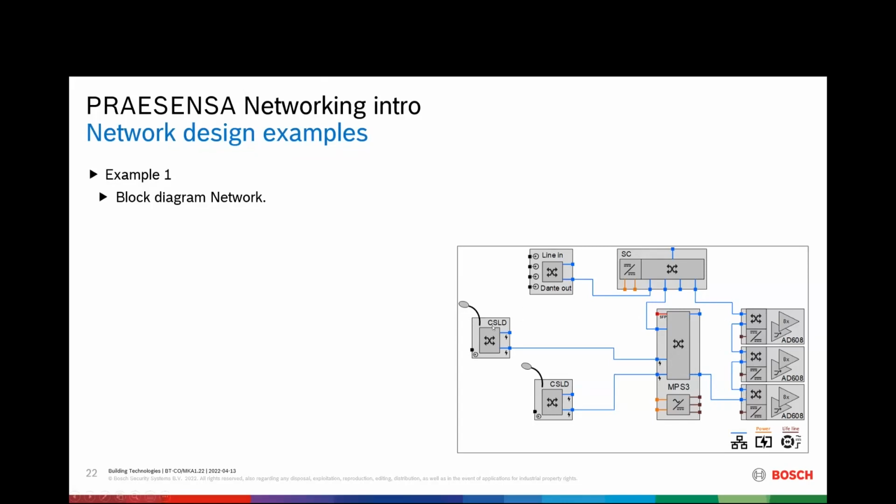Here we have a call station and a backup call station. In this case, you could decide to have only a single connection to it, where one acts as a backup of the other. The MPS itself also has a lot of redundancy inside already. It is a component with 3 highly integrated, separate, fully isolated circuits, so it is a higher integrated level of redundancy inside the MPS. But for the network diagram itself, this would be a solution for this first setup.